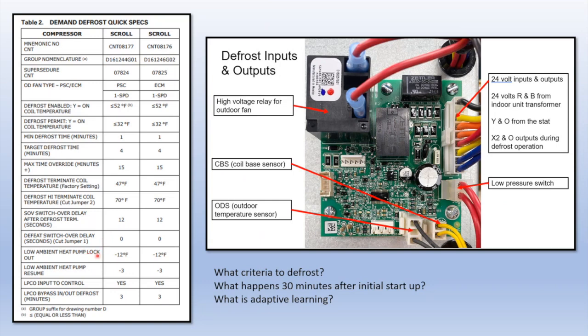There's also a low ambient heat pump lockout at -12 Fahrenheit. So what that means is at -12 Fahrenheit, if it receives a Y signal, it will not run the outdoor unit, but it will put a signal back out the X2 terminal. And the X2 is going to be hooked up to your W on your indoor unit, and it's going to turn indoor heat on. It's not going to resume heat pump operation until it rises to -3 Fahrenheit. So if you have a heat pump that you give a Y signal and it doesn't turn on, you may see a soft lockout error code on your fault light. You might want to look at the calibration of your outdoor ambient. And if you give it a Y signal and your furnace turns on, same thing.